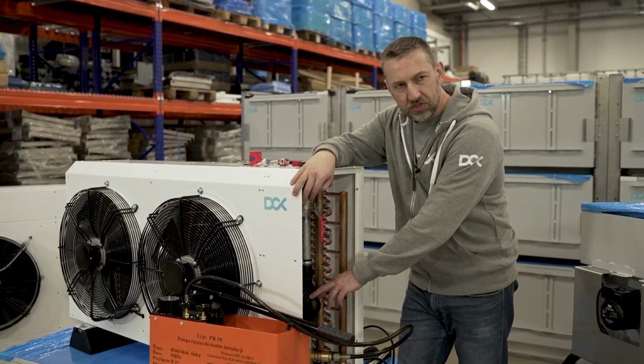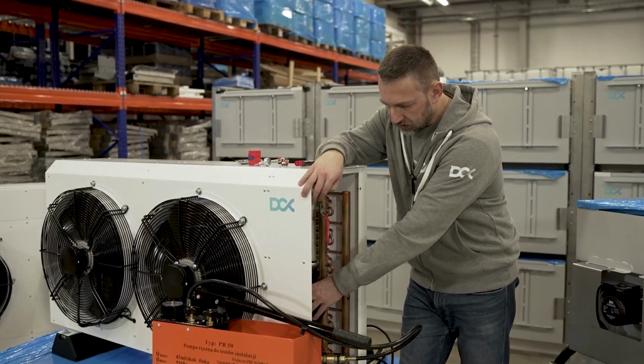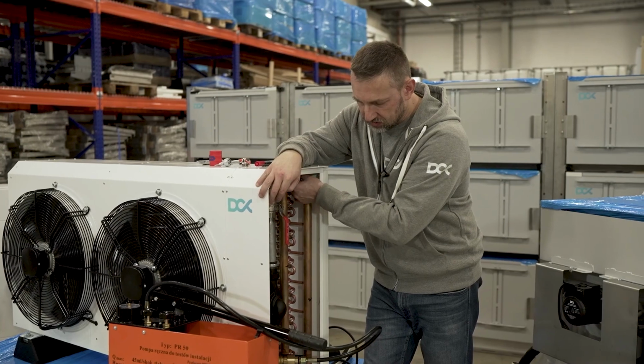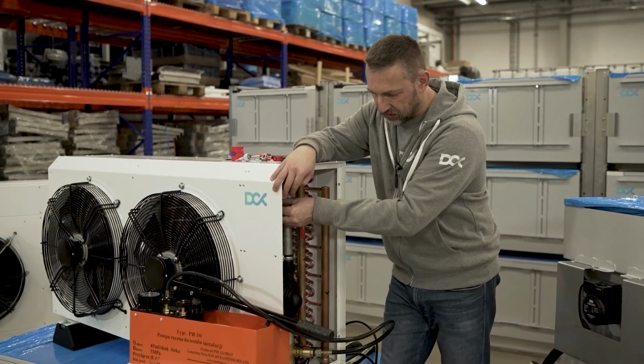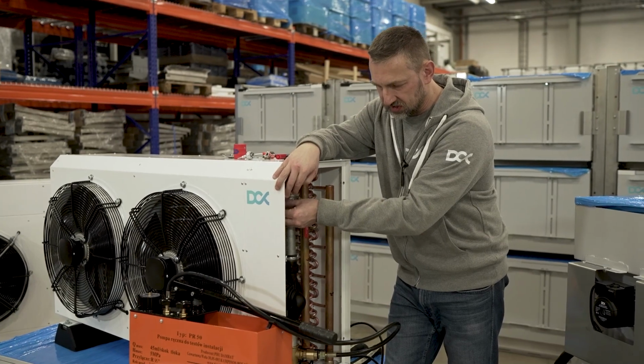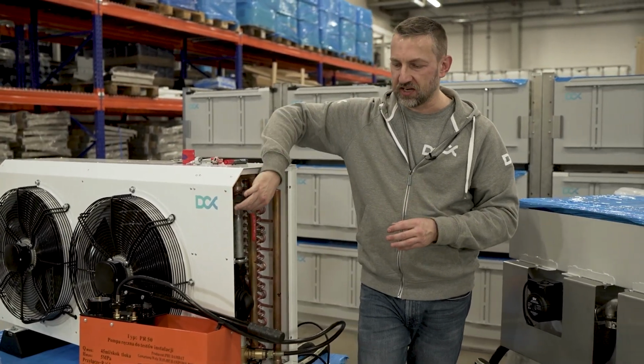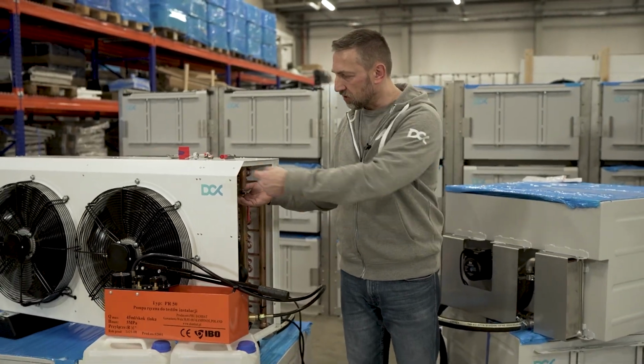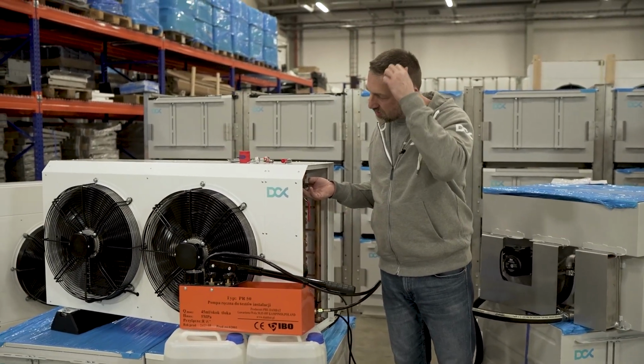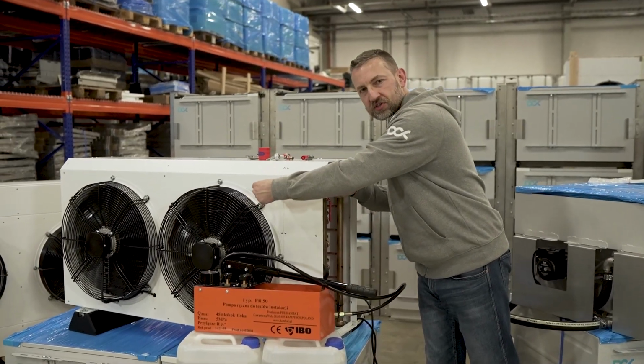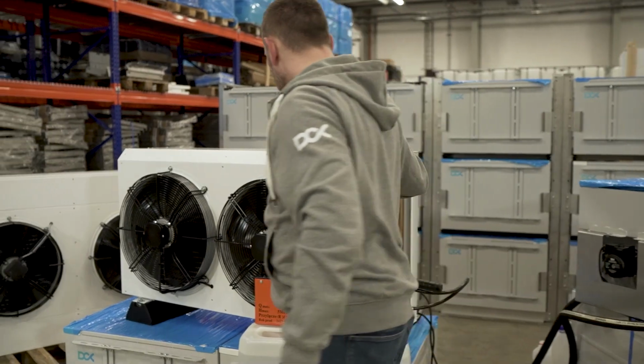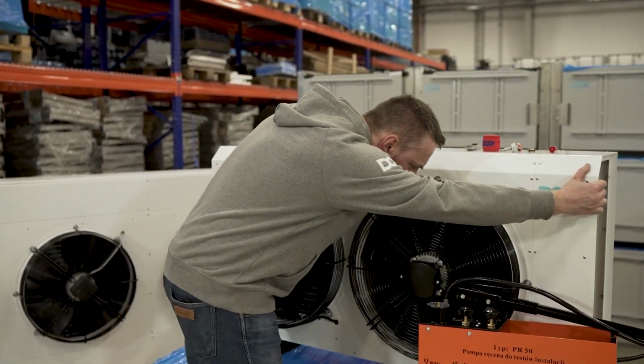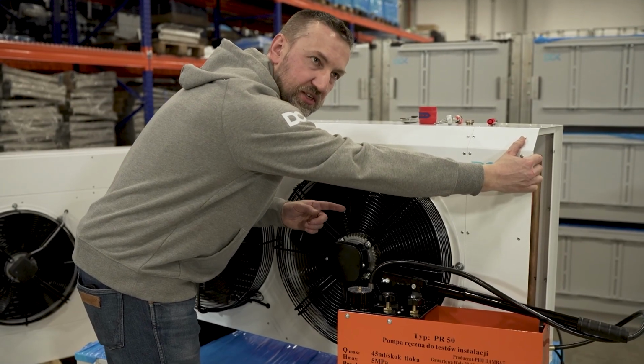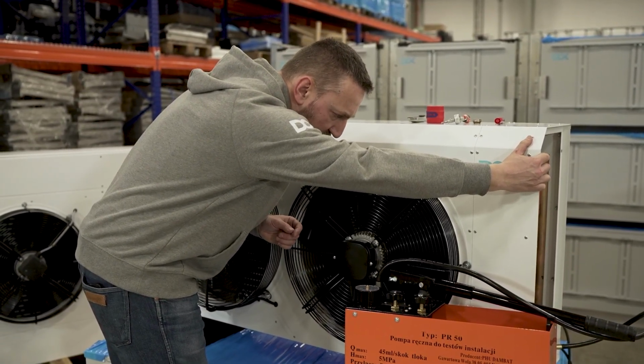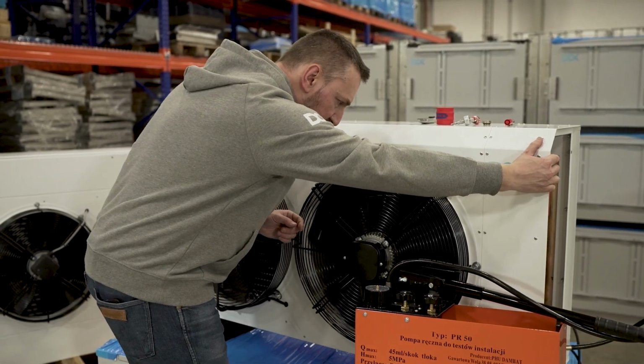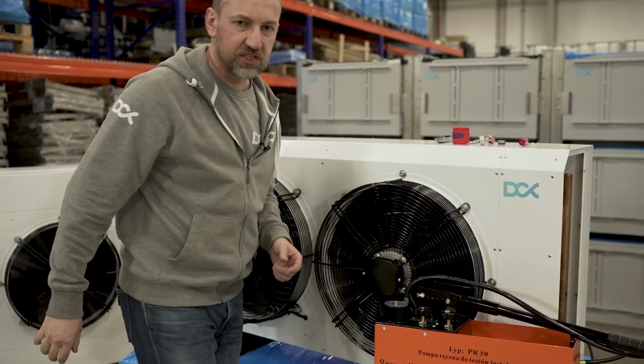And again, there may be some dripping from that pump. As you can see, it's a little bit noisy. So that means that it can be airlocked. I still need to add some water into the system, because the pump should circulate almost silently. So let me see how the pump is behaving on the other side. I need you to see through the fan, because the pump head is on the other side. I will start the pump right now, and I will observe what's happening here, and I will see the digits on the LCD screen. You'll be able to see that. And I see 28, which is not enough. It just means that I need to add some additional water into the system. So let's do that.